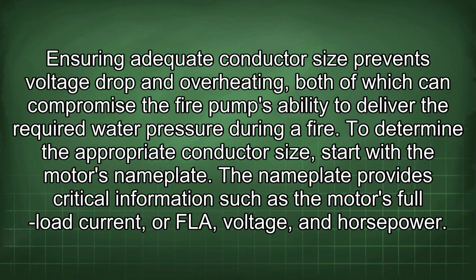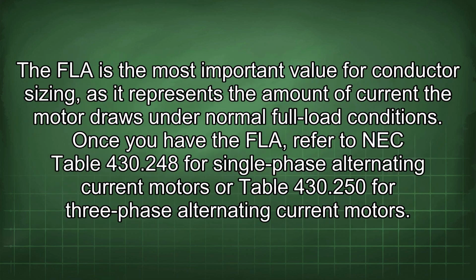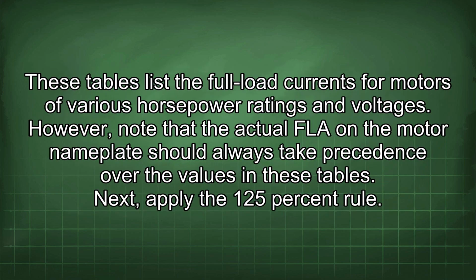To determine the appropriate conductor size, start with the motor's nameplate. The nameplate provides critical information such as the motor's full load current, or FLA, voltage, and horsepower. The FLA is the most important value for conductor sizing, as it represents the amount of current the motor draws under normal full load conditions. Once you have the FLA, refer to NEC Table 430.248 for single-phase alternating current motors or Table 430.250 for three-phase alternating current motors. These tables list the full load currents for motors of various horsepower ratings and voltages. However, note that the actual FLA on the motor nameplate should always take precedence over the values in these tables.